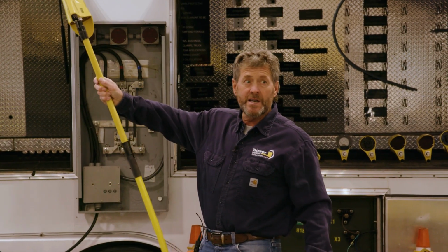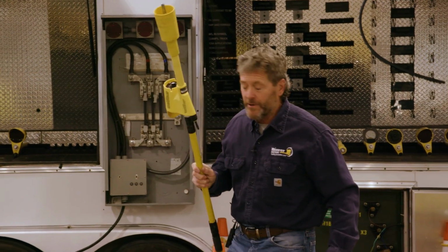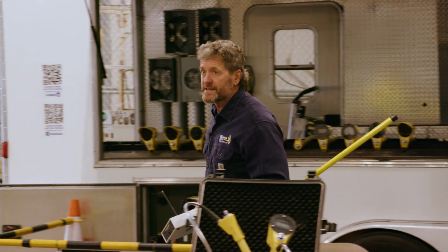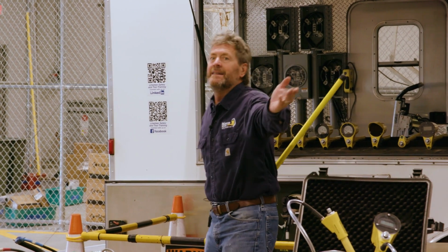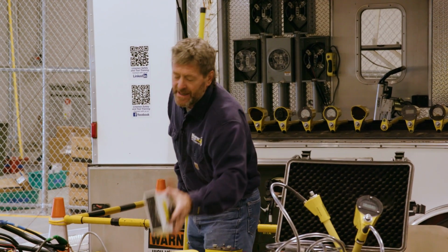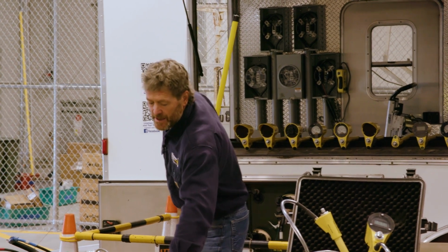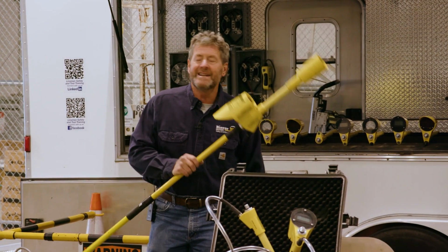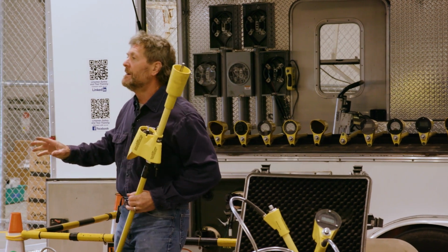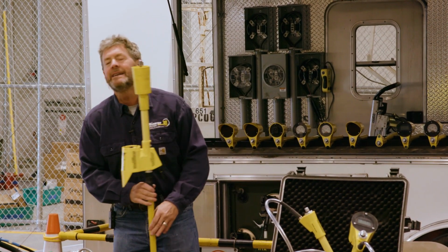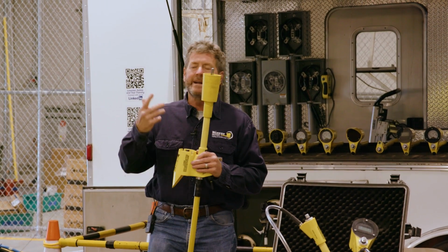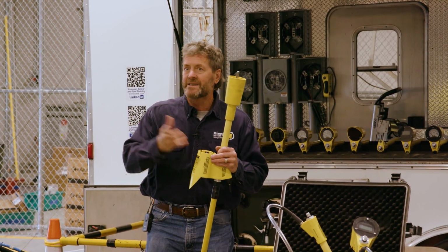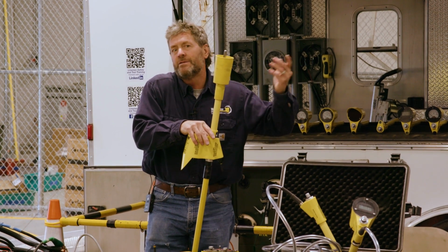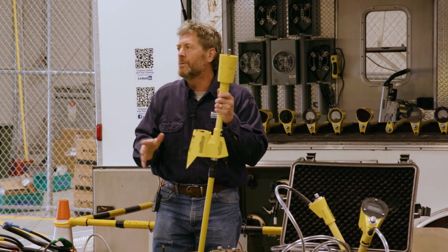Whatever conductor you touch, potential, don't care about. Whatever conductor you touch, if you get a white light and close to zeros, then that's A phase, same phase, because A is your reference. This is A phase, white light solid, this is your A phase reference. So you get zeros with a white light, that's your A phase. You touch any conductor, any height, any span, any dimension, any name, any title, and you get a blue light, 120 or close to 120, that's your B phase. Red light 240, C phase. It's real simple, and it's that fast too.